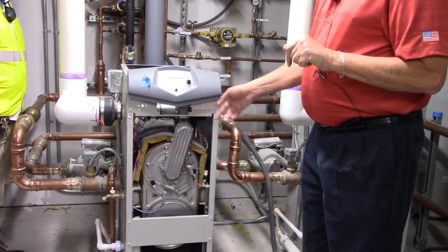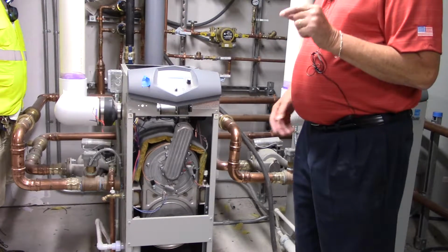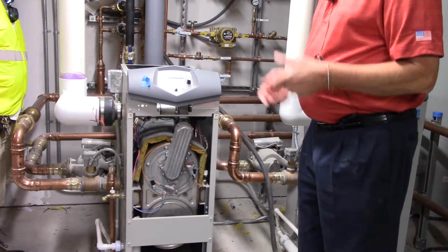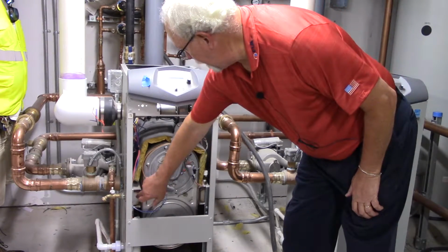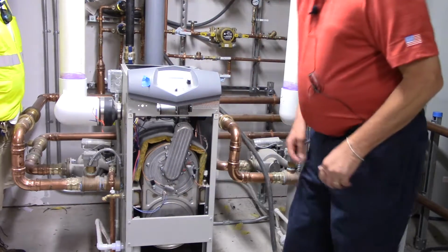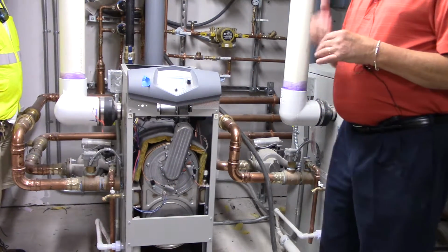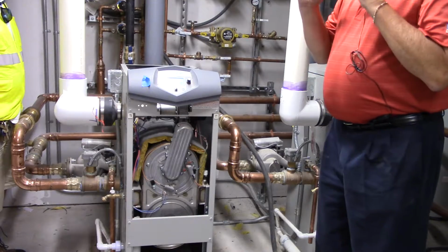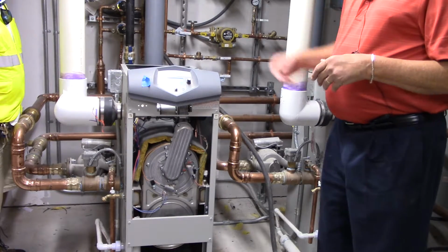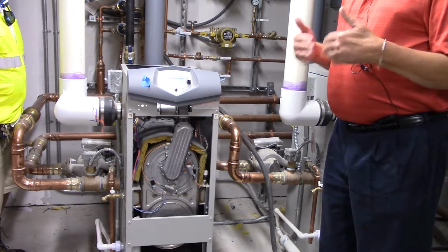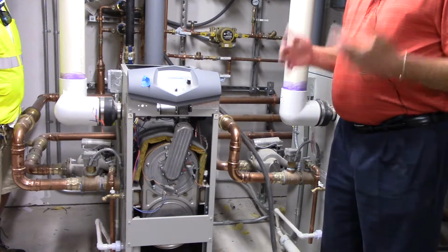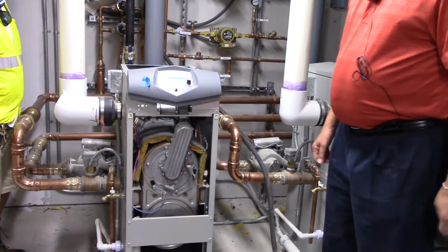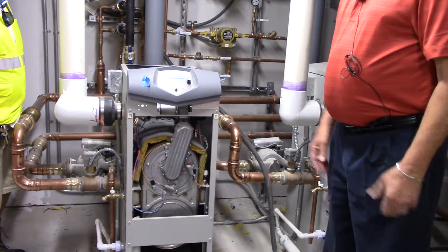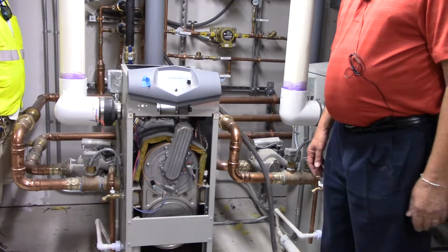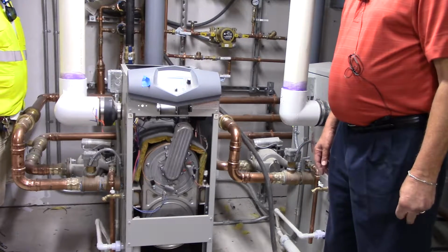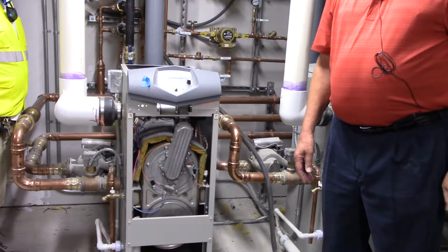The water tubes in these units are individual tubes. Each one is welded to a supply and a return header. So here's your return header, here's your supply header, and they're each welded. So you have a flue passageway in between the units, and this fan has to blow your byproducts of combustion out. If those passageways get filled up and it can't do it, you can have some problems. So that's why it's important to clean it. I'd say to clean one of these is an hour and a half, 2 hours tops. Do a nice job. Anybody have any questions?